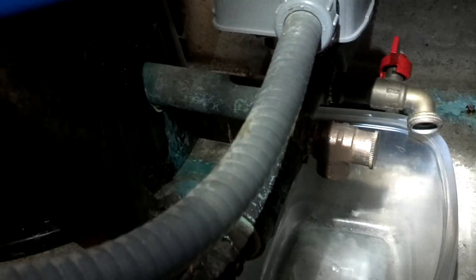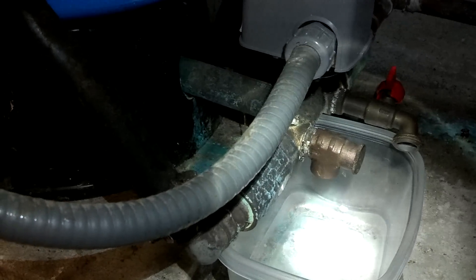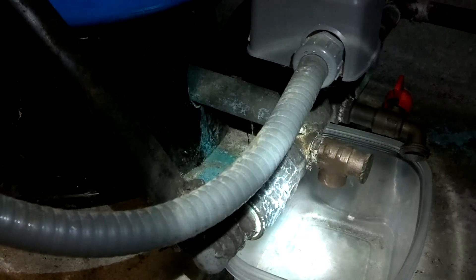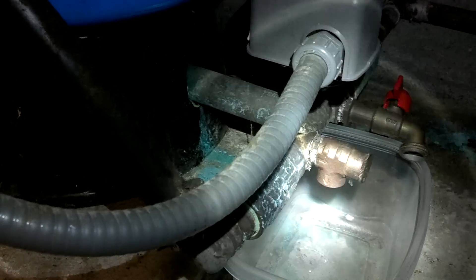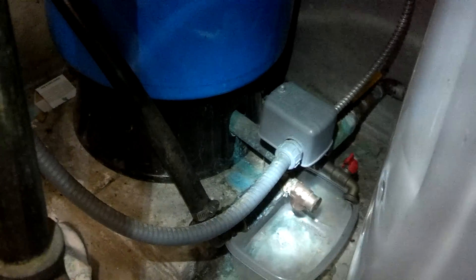It's a relief valve. When the gauge over there gets to 80, this copper valve right here lets water out. At 70, when the pressure goes up to 70, it doesn't do anything, but when it hits 80 or 85, it lets water out of there. We found a small flood down here in the basement, and that's straight from our well in the ground into that right there.